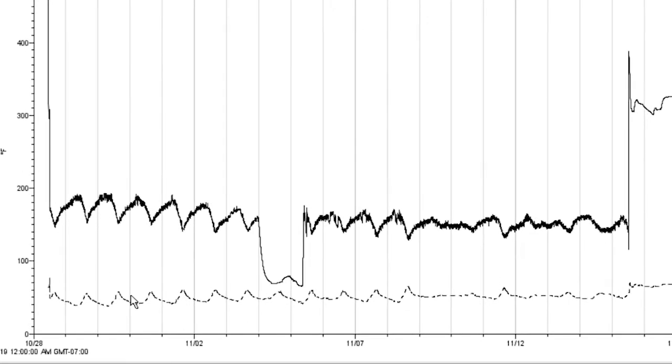So you can see here that we have a pretty clear pattern also with the outside air temperatures rising. And you can see that it lines up with the supply temperature dropping pretty consistently across the board. Of course, minus the anomaly of the section where the boiler was offline. But you can see that these peaks align with the valleys on the supply temperature. And that's what we're looking for, is for the control system to lower the supply temperature when the outside air temperature is higher. That's the function of the boiler reset function. So just in looking at this data, I can be pretty confident that our boiler reset function is working properly.